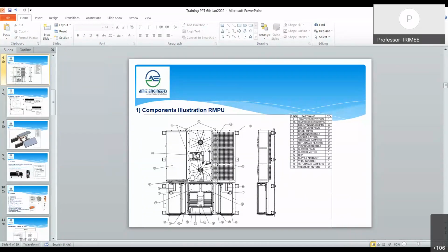And these are 2 axial condenser fans. And these are the 2 drain pipes through which the condensed water from the evaporator is routed as a stainless steel pipe inside the system, and it protrudes outside. From here it will be connected through the drain arrangements. And here there are the 2 heat exchangers, that is condenser coils, and there are 2 accumulators in the suction line of the system, and fresh air dampers. See, this system has fresh air dampers and 2 return air dampers. Normally in LHB coaches we have dampers, but this one is automated, with damper actuators which we can control as logic. There are 2 evaporator coils and blower fans, 2 fans with one.